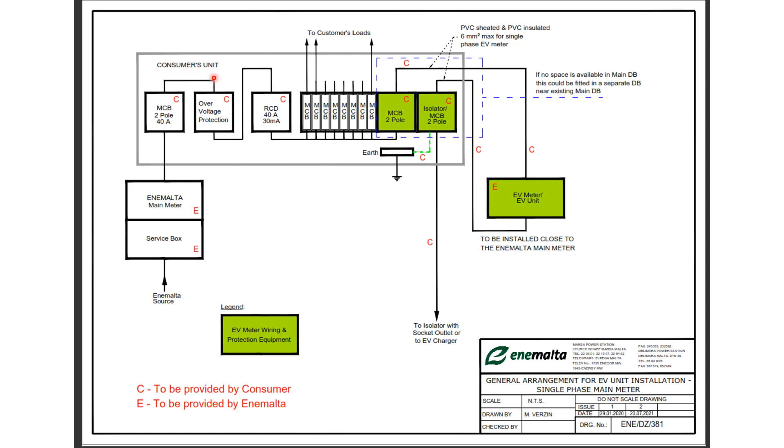Now the minimum size of cable which is to be used until we go into the individual MCBs is six millimeters squared, but sometimes it will be a bit larger, for example 10 millimeters squared. But according to the IET regulations BS7671, for 40 amperes we can have six millimeters squared on a single phase system.